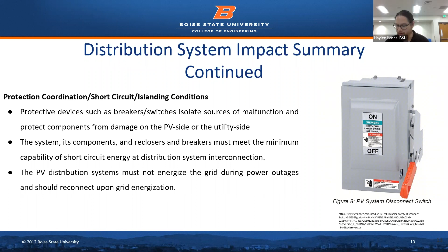We designed our PV systems with protective switches and reclosers to provide protection to sensitive components on both sides of interconnection. Theoretically, short circuit studies will be needed to ensure these switches are rated to the capacities required for our systems. These components allow our systems to island during power outages and prevent energizing the grid while still providing energy to the load. Upon re-energization and no faults detected, the reclosers will reconnect the PV systems to the grid.